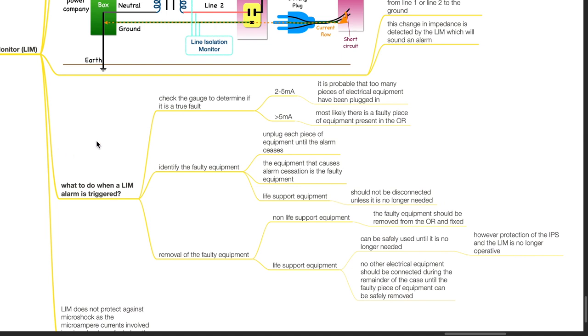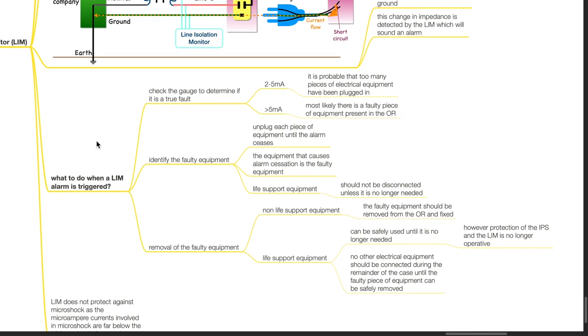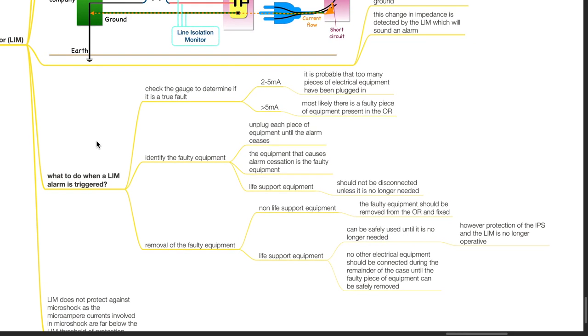What to do when a LIM alarm is triggered? Check the gauge to determine if it is a true fault. If it is 2 to 5 milliamps, it is probable that too many pieces of electrical equipment have been plugged in. If it is more than 5 milliamps, most likely there is a faulty piece of equipment present in the OR. Identify the faulty equipment by unplugging each piece until the alarm ceases. The equipment that causes alarm cessation is the faulty equipment and should be repaired. For life support equipment, these should not be disconnected unless no longer needed. Remove the faulty equipment. For non-life support equipment, remove and fix it. For life support equipment, it can be safely used until no longer needed; however, protection of the IPS and LIM is no longer operational. No other electrical equipment should be connected during the remainder of the case until the faulty equipment can be safely removed.